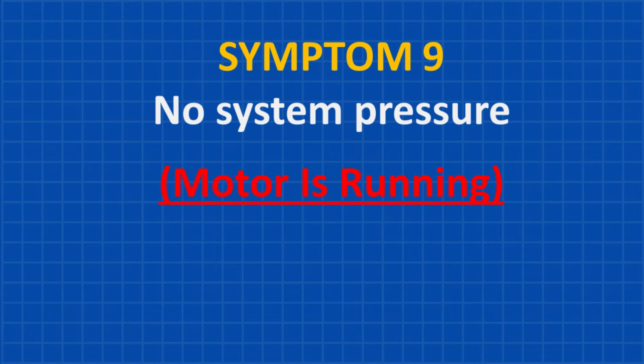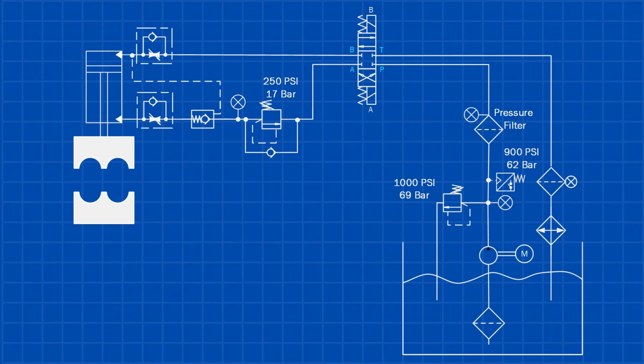Symptom 9. No system pressure, but the motor is running. There are usually three main causes for this problem. 1. The relief valve could be failing, allowing oil to bypass back to the tank. 2. The pump might be sucking air, preventing it from reaching the set pressure. 3. The pump itself could have failed.